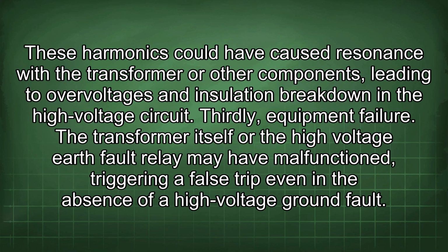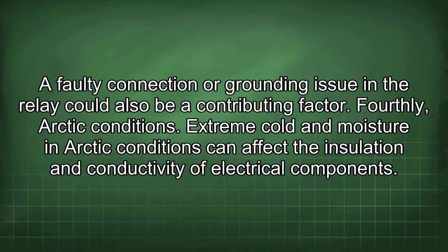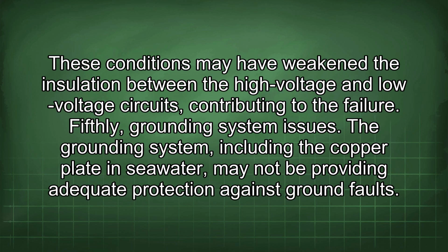The transformer itself or the high voltage earth fault relay may have malfunctioned, triggering a false trip even in the absence of a high voltage ground fault. A faulty connection or grounding issue in the relay could also be a contributing factor. Fourthly, Arctic conditions. Extreme cold and moisture in Arctic conditions can affect the insulation and conductivity of electrical components. These conditions may have weakened the insulation between the high voltage and low voltage circuits, contributing to the failure.